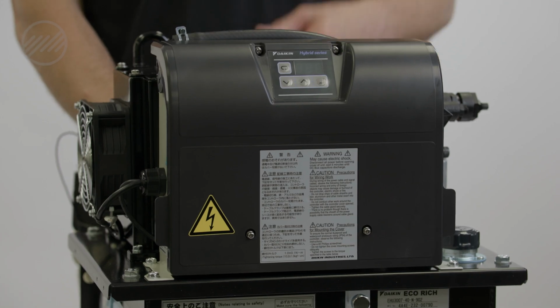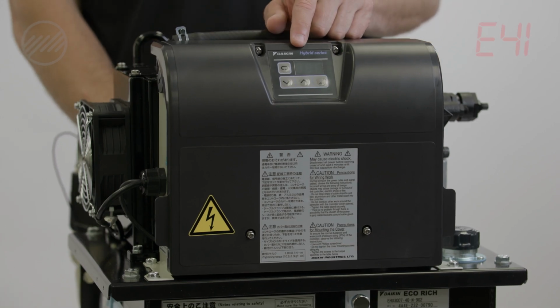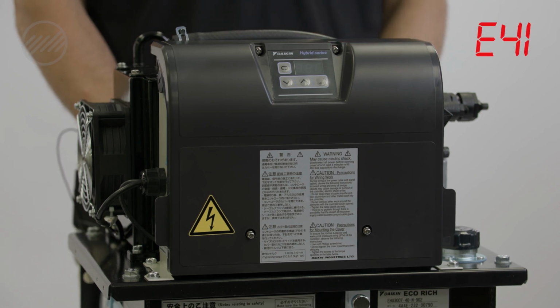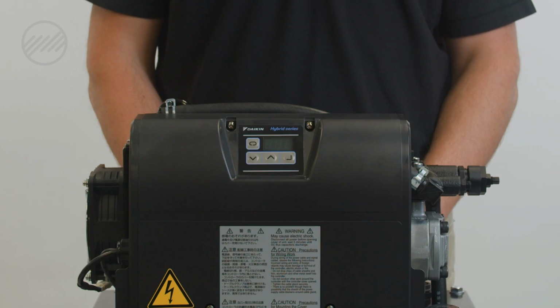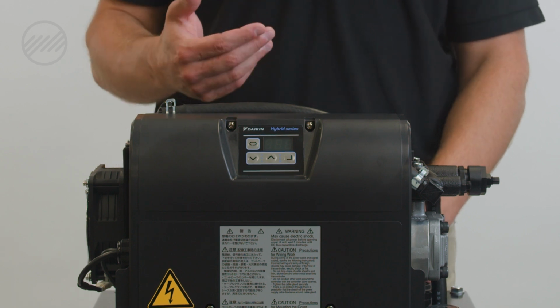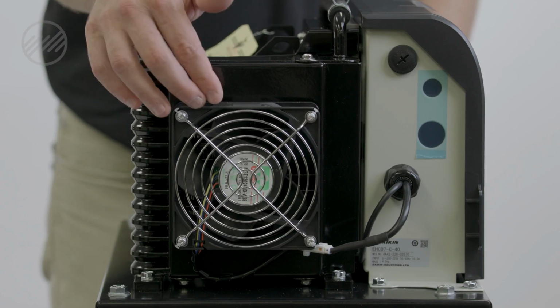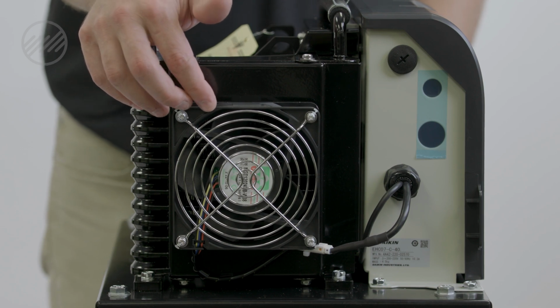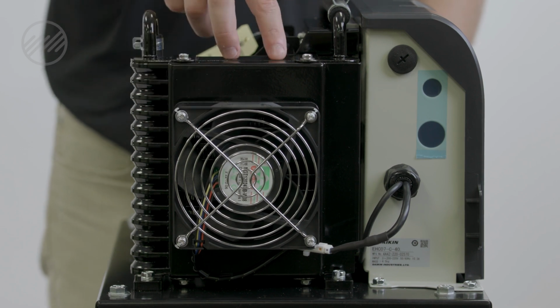If your Daikin EHU is displaying an E41 alarm, this is an indication that your motor temperature has exceeded 85 degrees Celsius. There are several factors that can contribute to this. First thing we need to check is that our fan, our cooling fan, is rotating and is not plugged.